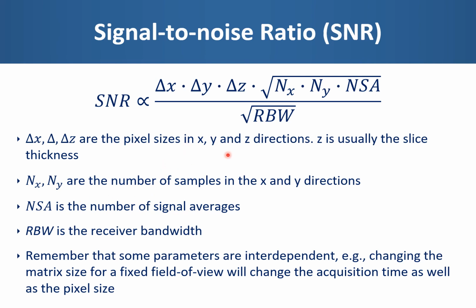The SNR is also proportional to the square root of the number of samples in the frequency encoding and phase encoding direction, as well as the square root of the number of signal averages. If we just repeatedly acquire the data, add the data together and then divide by the number of averages, then we can improve the signal-to-noise ratio. The signal-to-noise ratio is also inversely related to the square root of the receiver bandwidth. If you're using this equation to look at changes in signal-to-noise ratio, remember that some parameters are interdependent, so that if we change the matrix size for a fixed field of view, we may also change the acquisition time as well as the pixel size.